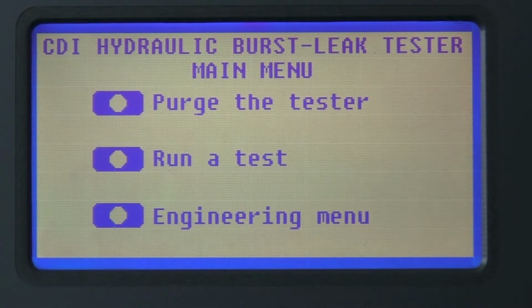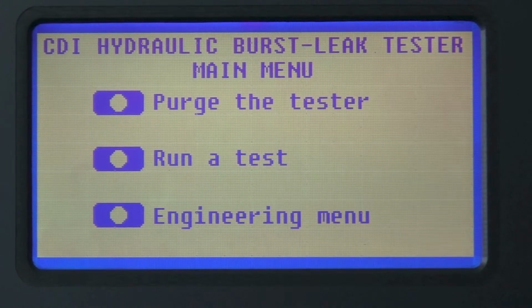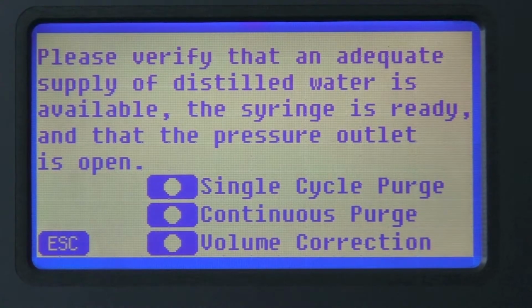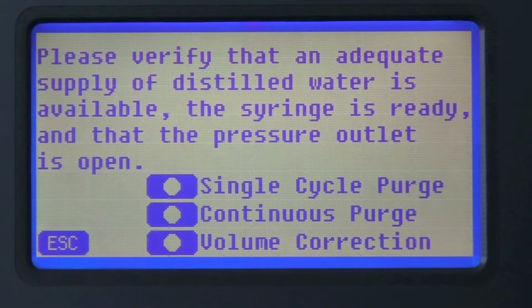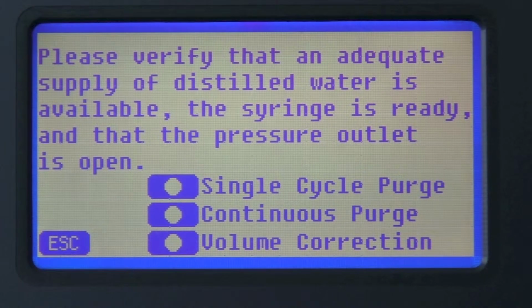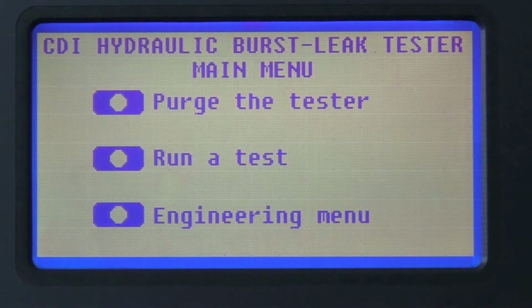Here we have choices: purge the tester, run a test, and the engineering menu. Purge the tester is what should be done every morning, and I'm going to select that. It describes it briefly. We have a single cycle purge, a continuous purge, and volume correction. We'll discuss volume correction another time, but the single cycle purge and continuous purge are covered in other videos on how to purge the HBLT. We'll escape back to the main menu.